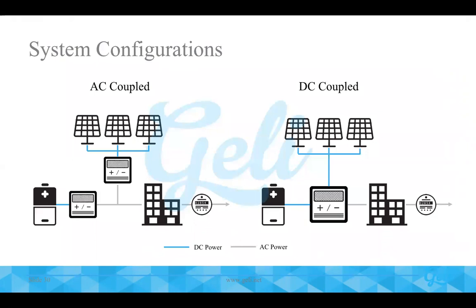For residential applications or microgrid off-grid applications, DC coupling is the most popular choice. But for commercial and industrial systems, a majority are AC coupled, meaning the solar is converted to AC power, and if it's charging the battery, it has to be reconverted to DC power to be stored. There's an inherent efficiency loss there compared to DC-DC conversion.